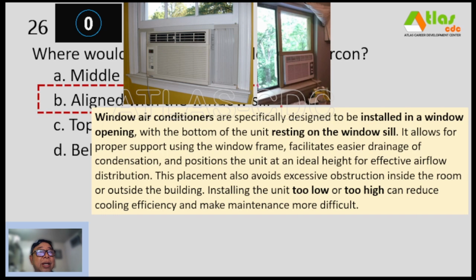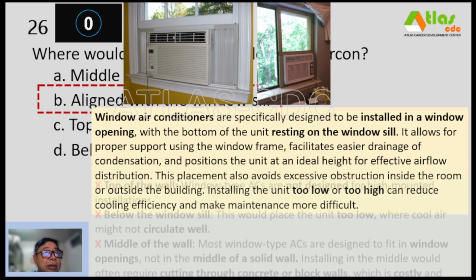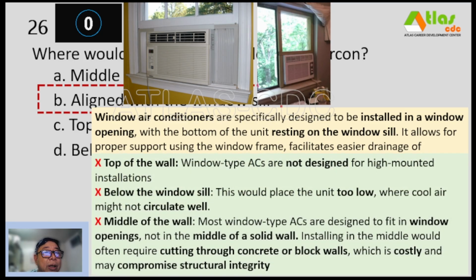So ayan, sa mga nasa baba talaga siya ng window portion, nasa window sill na area. Top of the wall, window type ACs are not designed for high mounted installations. So masyado mataas naman yon, no? And below the window sill, this would place the unit too low, where cool air might not circulate well. And middle of the wall, and most window type ACs are designed actually to fit in window openings, not in the middle of a solid wall. So installing in the middle would often require cutting through concrete or block walls, which is costly and may compromise structural integrity.